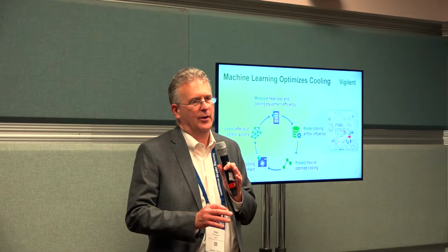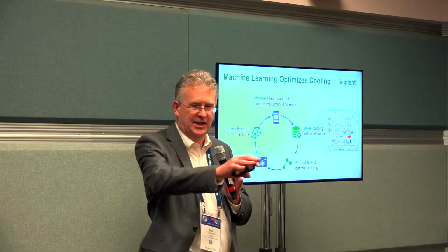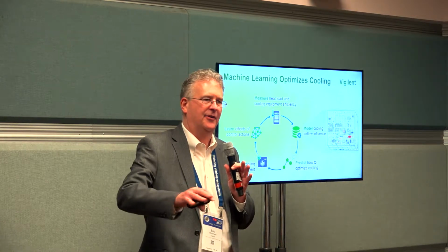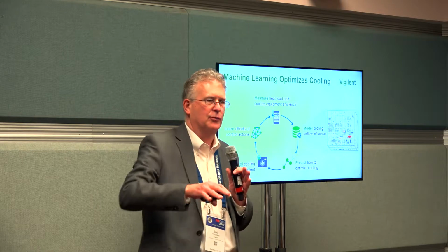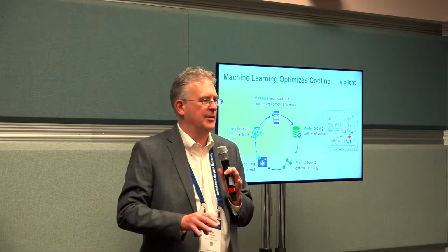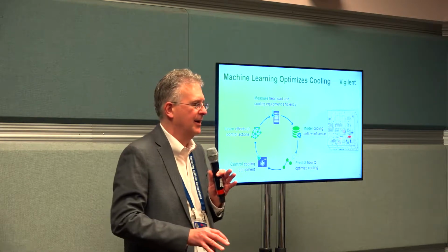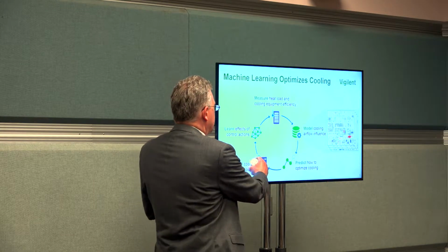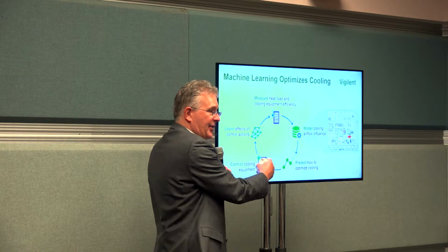It will figure out that with certain units on or certain fan settings, all the temperatures will be met using the minimum energy, and it develops a predictive model of that. It then starts control. It takes about a day to do that, and then it goes into control mode, turning units off, fans down or up, and meets those temperatures.